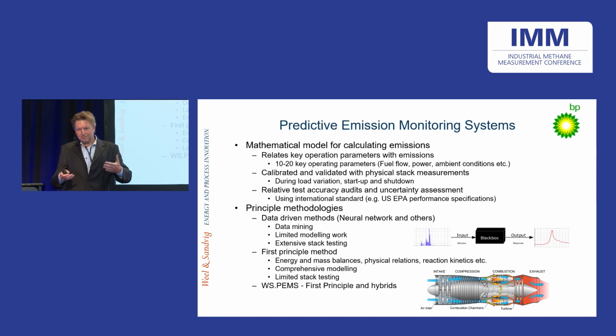All PEMS systems combine the models with temporary stack sampling, for calibration and validation purposes. There are two main types of technology. First, the black box approach, where you do a lot of stack sampling, record all the process values, and build an implicit model relating input to output. The advantage is you don't need to know much about the emission sources, but training the system requires a significant amount of stack testing.